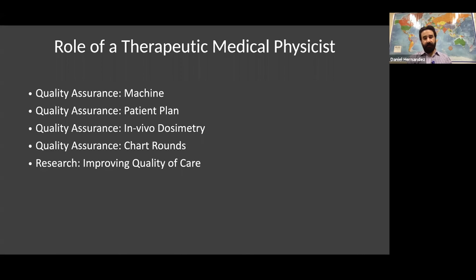These machines typically last somewhere on the order of 10 to 20 years, and so that machine needs to be monitored constantly. We check our machines daily, a rudimentary output check of the machine. We check them on a monthly basis, and we even check them on an annual basis. From year to year, these machines vary. Well, we have a tolerance that we allow them to fluctuate, and our threshold is 1%. So they have to remain constant in pretty much all of those parameters that we just saw, all of the motion of the gantry and the leaves, in addition to the energies and the actual output of the machine, to within 1% year after year for up to 20 years, which is pretty remarkable that they're that stable.